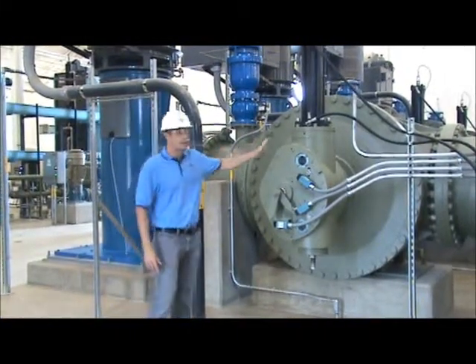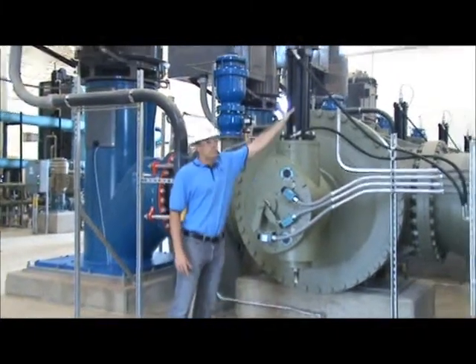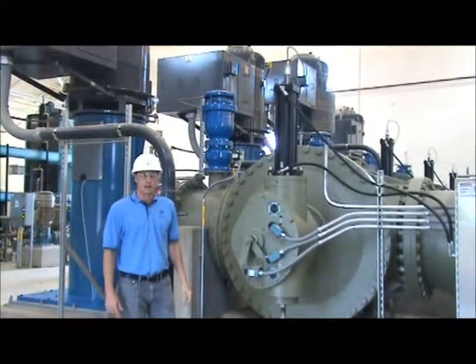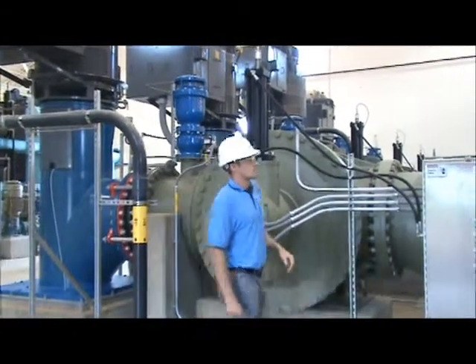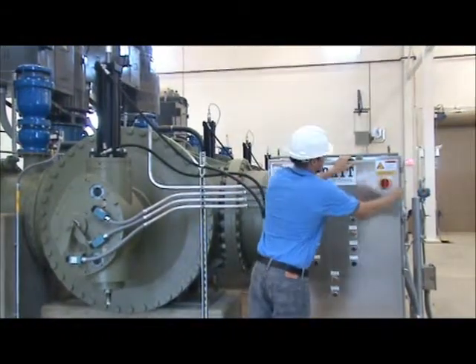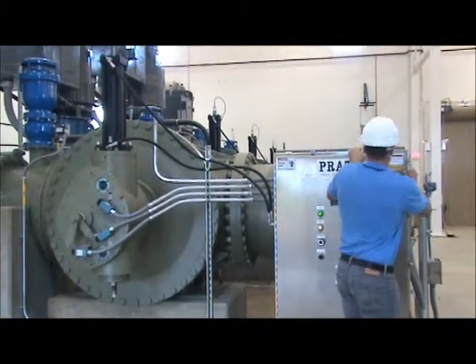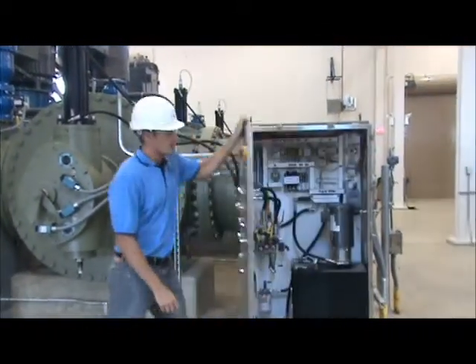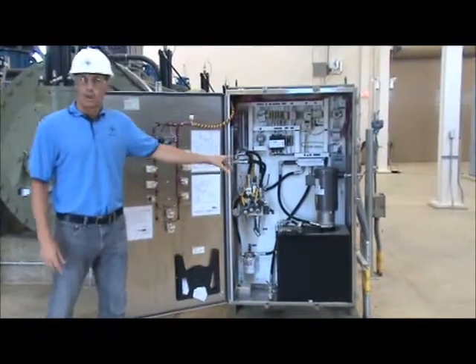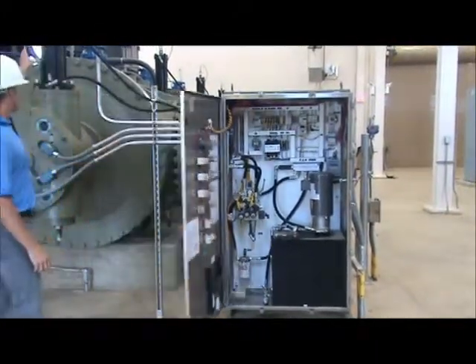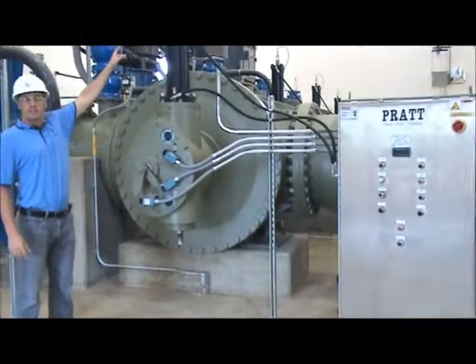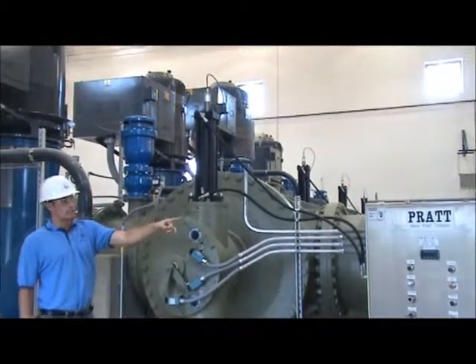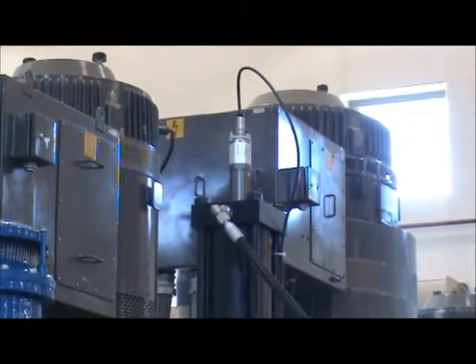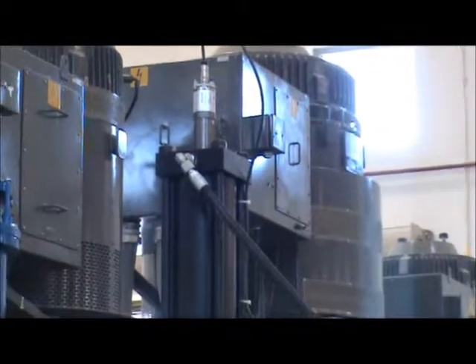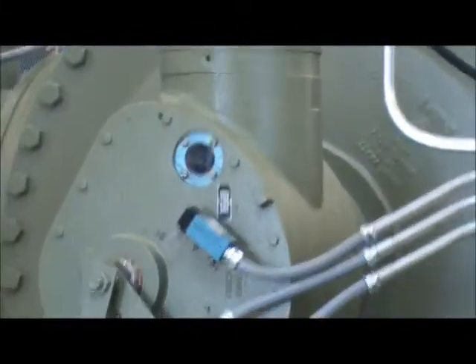Downstream of the pump is the hydraulic cone valve. This hydraulic cylinder controls the opening and the closing of the valve. There is a hydraulic pump which charges the accumulators, which in turn runs the valve. At the top there is our feedback sensor, which sends an analog feedback over to our controller, and then we compare that to our commanded position. And then there are also end of travel limit switches, which we use.